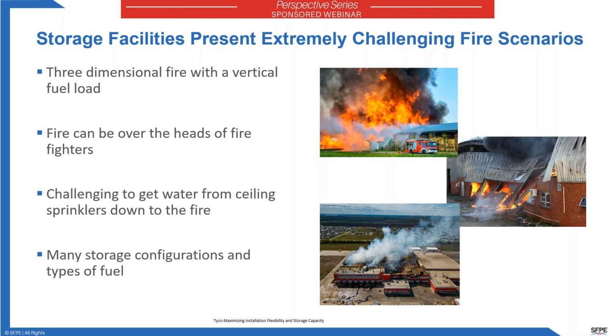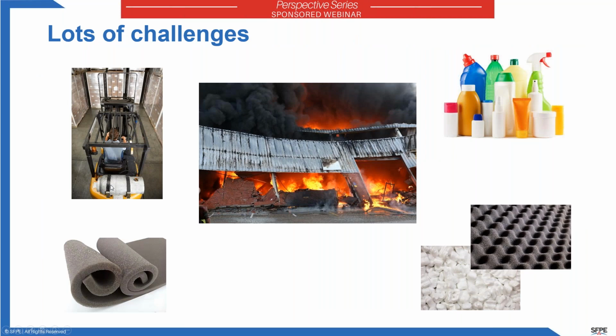It makes these very, very challenging scenarios. So figuring out what type of sprinkler or fire protection system to use is extremely important. So I mentioned things like commodity. When I mentioned occupancy type protection schemes that are in NFPA 13, extra hazard or light hazard or ordinary hazard type occupancies, when you're designing for storage applications, obviously one of the early steps is at least to identify what commodity you have. Storage protections are driven by the commodity and the challenge of protecting that commodity.